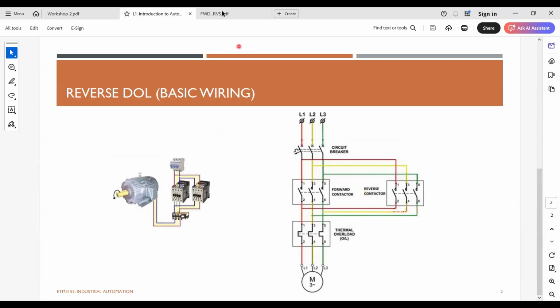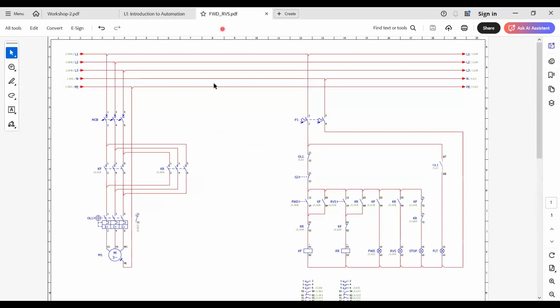Now we are moving to the single line diagram. You can see here, this is the power wiring and this is the control wiring. So the three-phase supply is coming from these terminals and this is the neutral wire and this is the protective earth. The protective earth is connected to the chassis of the motor. It does not go through any contact points. It is directly connected to the protective earth.